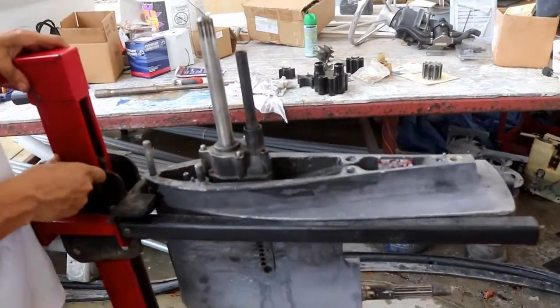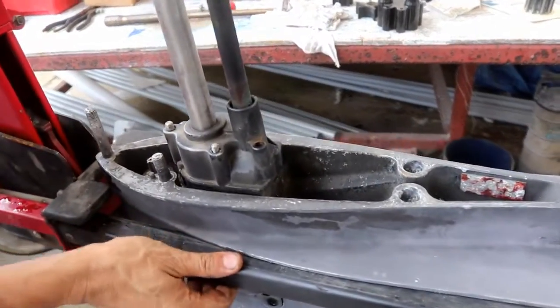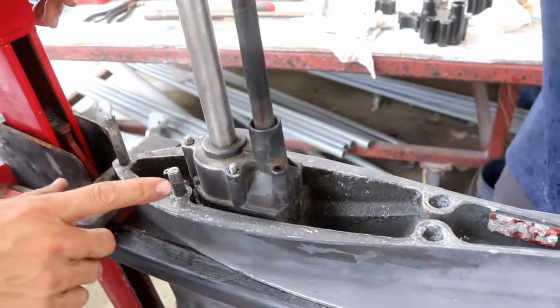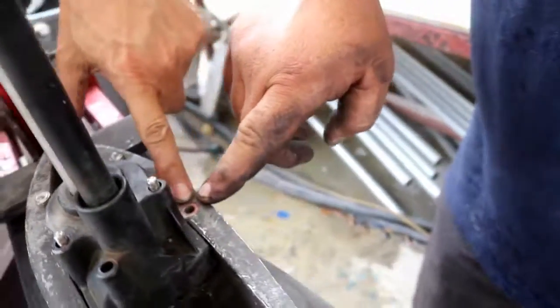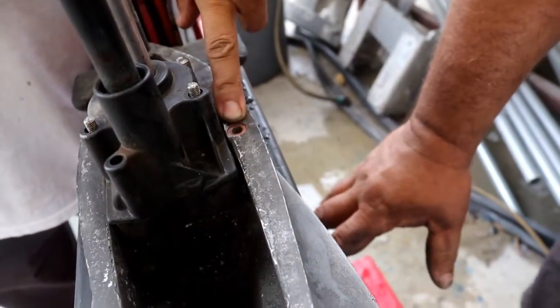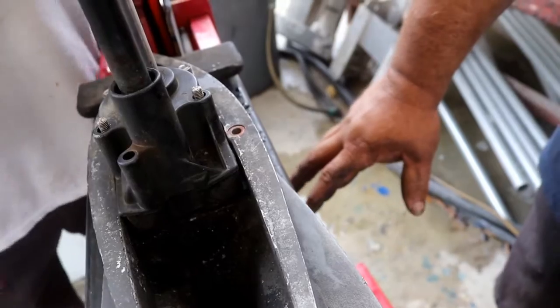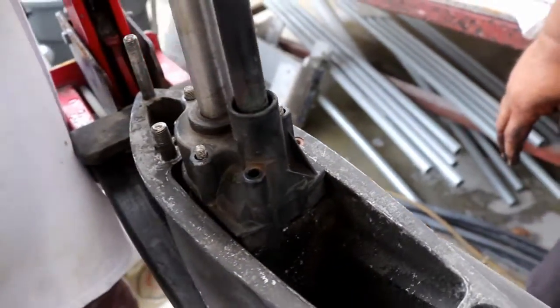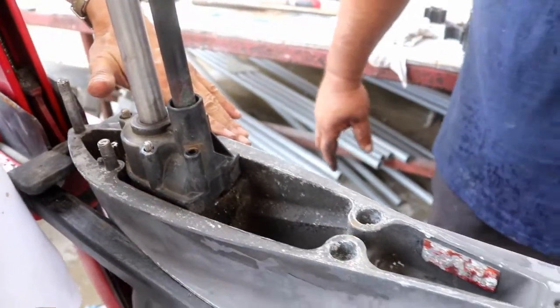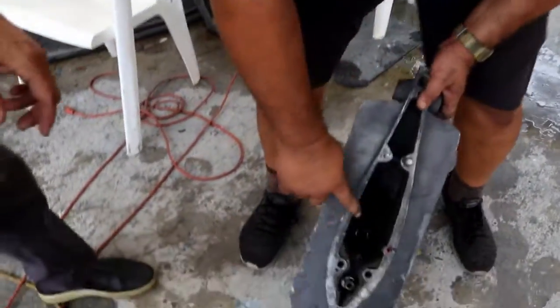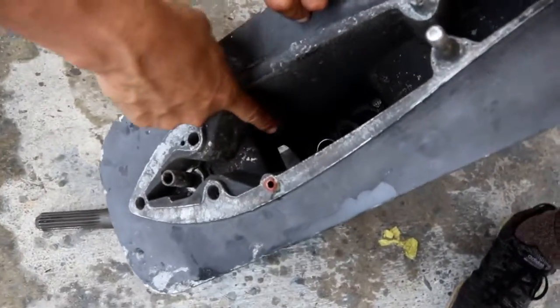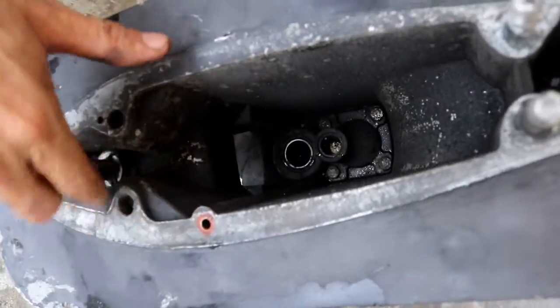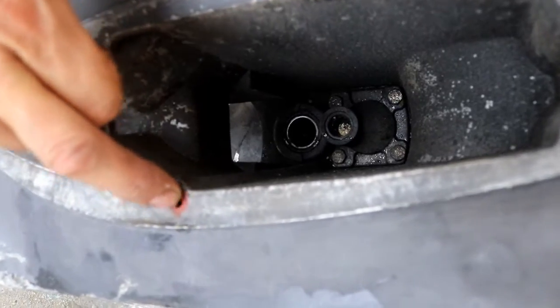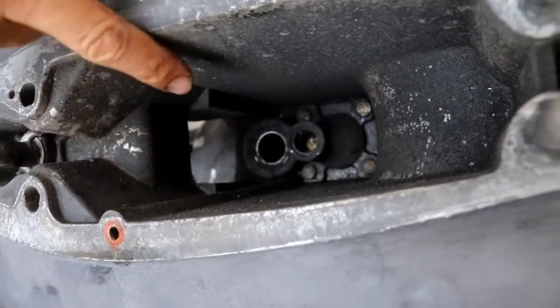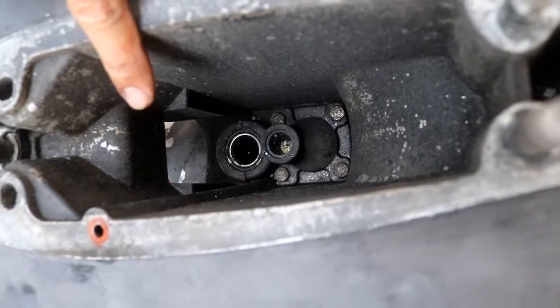Let me explain why: because you have an O-ring that keeps oil on the upper case, look at the oil, and you have oil in the lower case. Correct, we have oil in the upper case and oil in the lower case. And there's actually seals. Correct, look at the seals in there, we have the seals over there. And there's the transfer of oil from the top to the bottom. Correct, that's the O-ring for the transfer, and those are the seals.